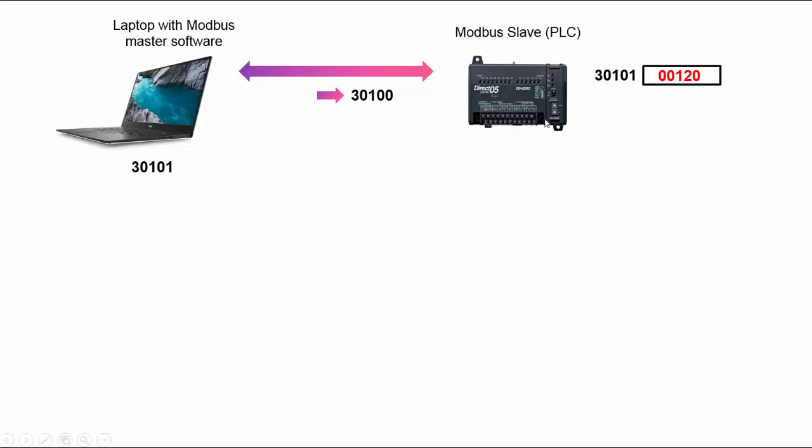However, this device now will see okay 30,100. Since it implements the Modbus protocol specification in the same way, it adds one, gets 30,101 and says okay they want 120, sends it back. Everybody's happy.